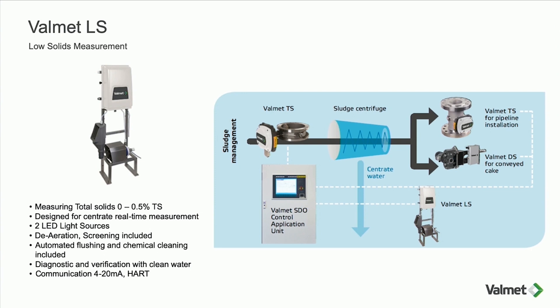The main challenge with centrate measurement is that the sample is very problematic — there's a lot of air, debris, and dirt build-up. Valmet LS is supplied as standard with de-aeration, screening to remove debris, and automatic flushing included to keep the measurement system clean. During the cleaning cycle we add chemical to keep the system as clean as possible. When flushing, we also measure the integrity of the light signal through water, so if the cell becomes dirty, a warning is given to the operator that action is required.